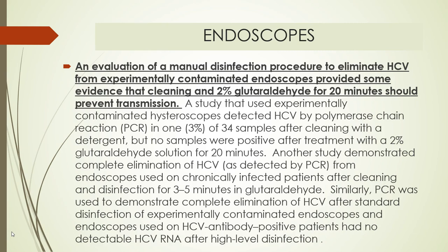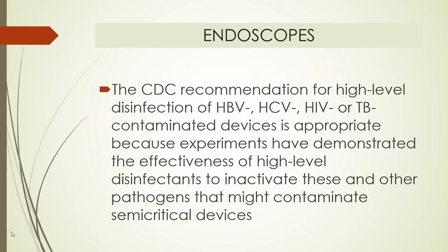Endoscopes can generally not be autoclaved. This requires disassembly. This requires appropriate scrubbing and cleaning, and then it requires appropriate sterilization. Typically, glutaraldehyde at a concentration of 2% is utilized for 20 minutes in order to prevent the transmission of disease. Endoscopes should be exposed to high-level disinfection to cover for tuberculosis, hepatitis B, hepatitis C, and HIV.